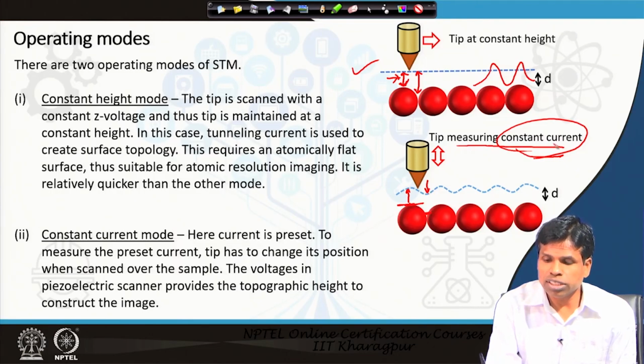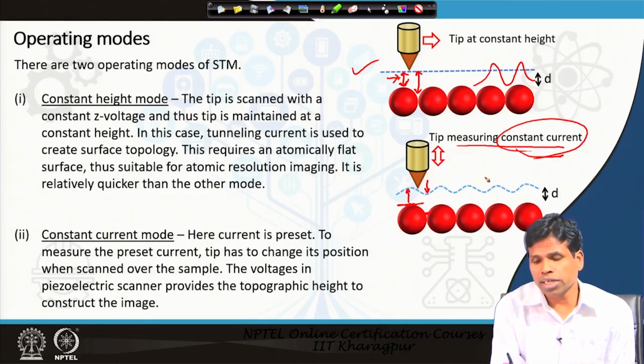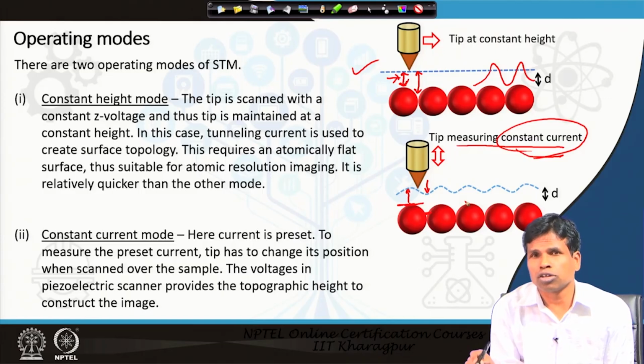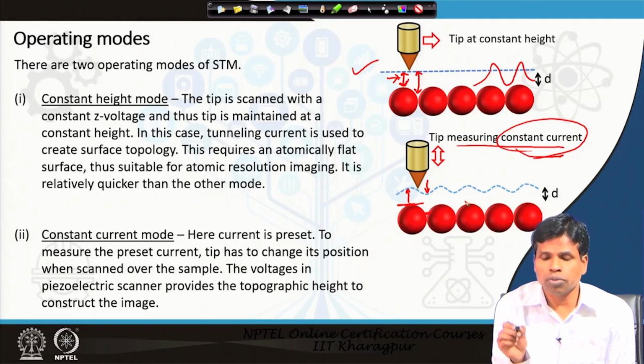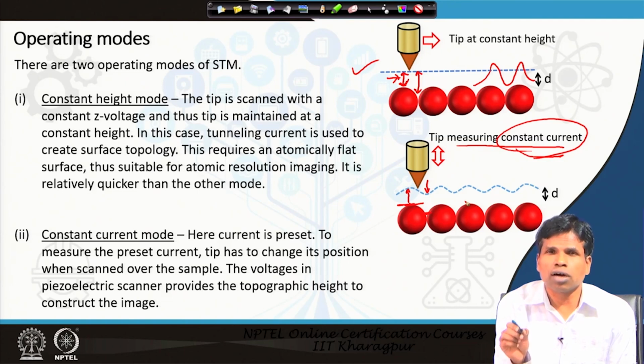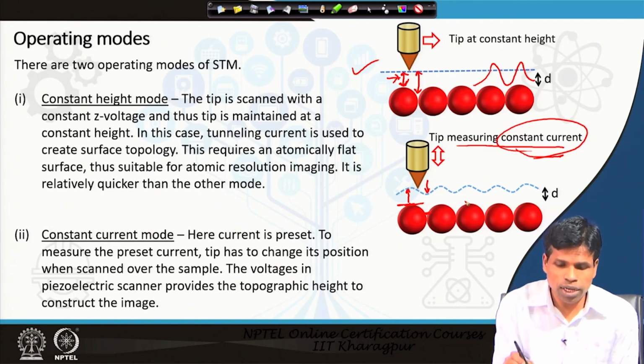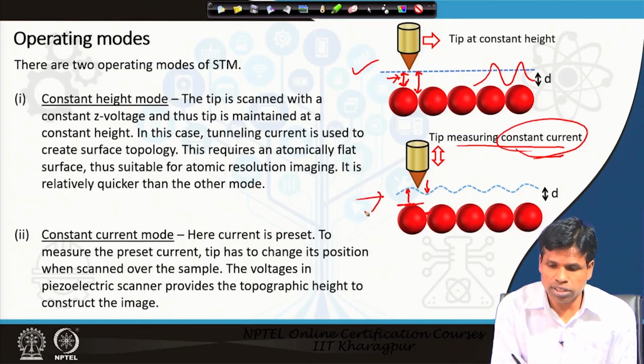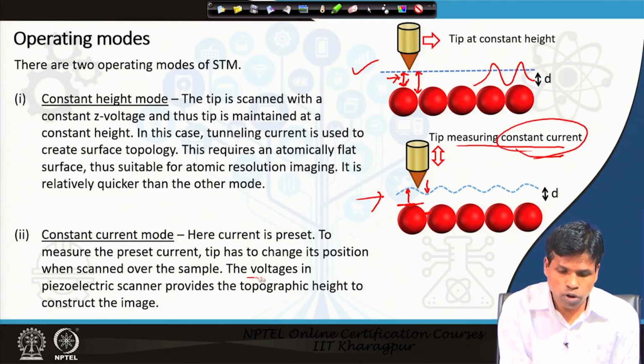And as we are measuring the constant current, we are making sure that the tip is not at all going to touch the sample, because as soon as it comes closer to the sample, it will measure a higher current, and the feedback loop will certainly stop the tip moving closer, because it already measured that much current. The feedback loop will give the signal that you are already reaching the value of the current, now you have to go upward. So this type of measurement, constant current measurement, is particularly done with unknown samples, and the voltage in the piezoelectric scanner provides the topographic height to construct the image.